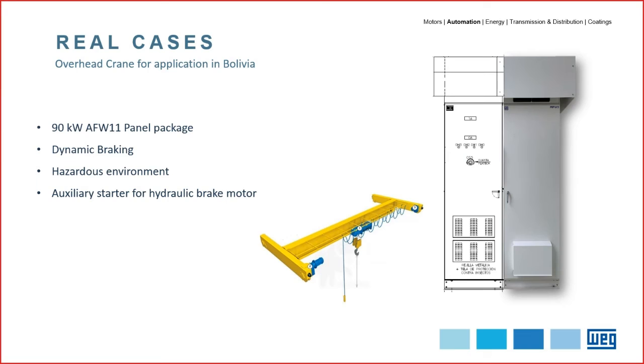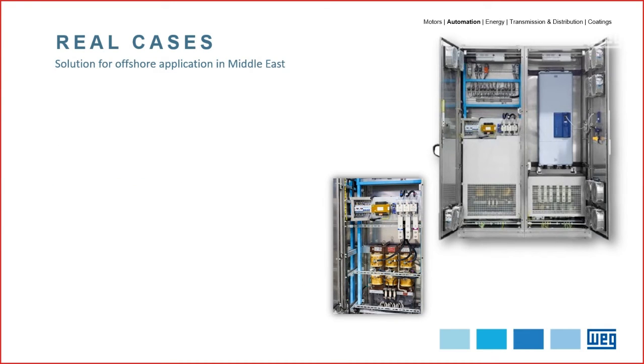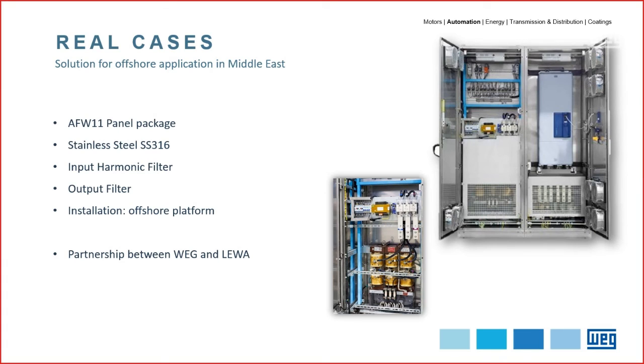Here we have an example of a 90 kilowatt VSD panel supplied to a customer in Bolivia. This panel was designed with dynamic braking and for operation in a hazardous area or environment. This was a very interesting project developed after a partnership between WEG and LEWA. All these panels were completely designed with a stainless steel enclosure for offshore application.